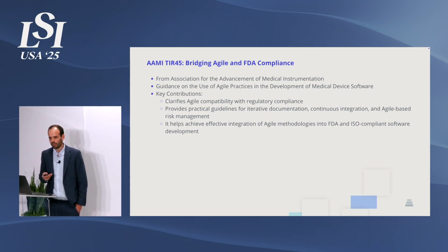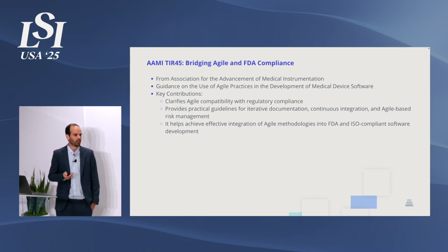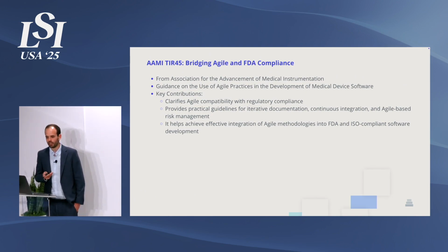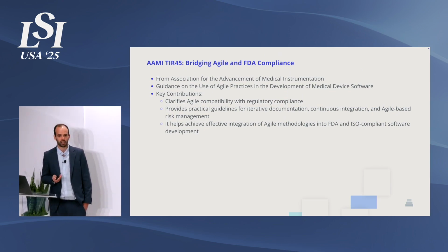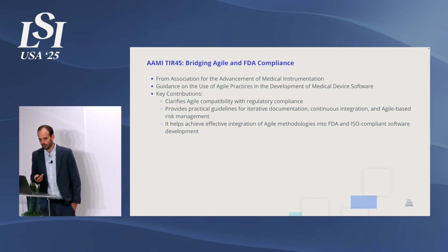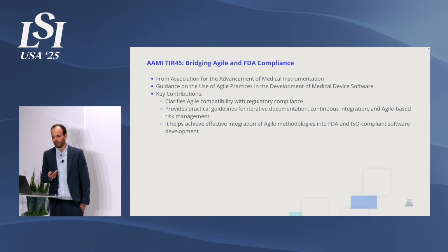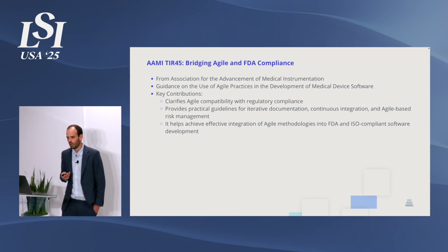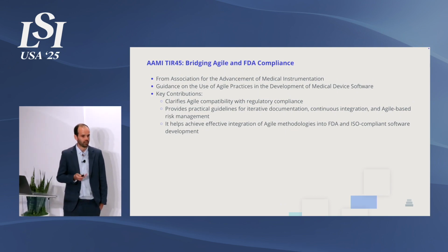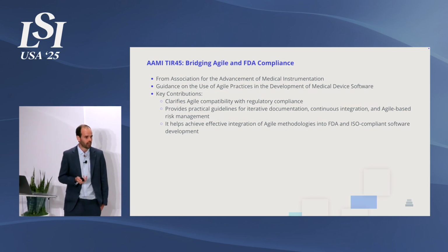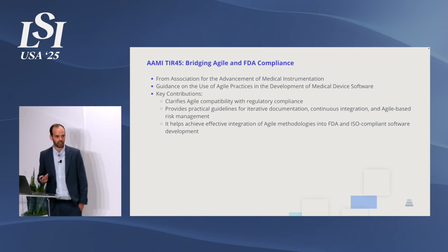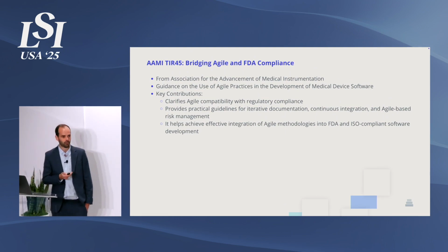To give a brief intro, we're going to be talking about AAMI TIR45. It's from the Association for the Advancement of Medical Instrumentation, and it is a guideline that first of all defines and validates that Agile can be used for FDA-regulated software, or regulated software in the medical device space. It clearly states that it's acceptable, and when you have it as guidance, it gives a lot of strength to the case of using Agile, and it's not only individuals supporting it.